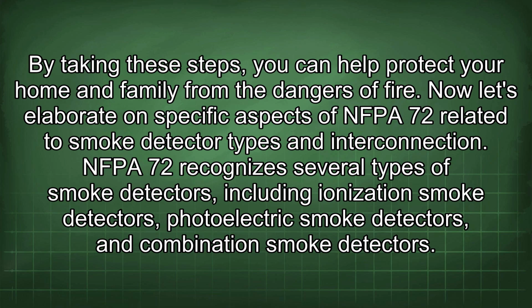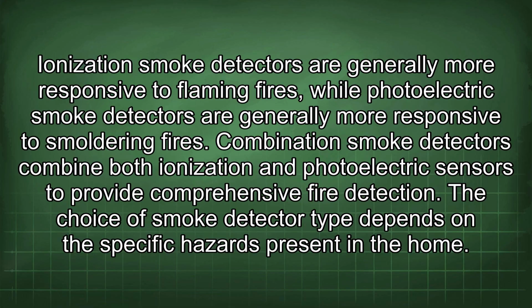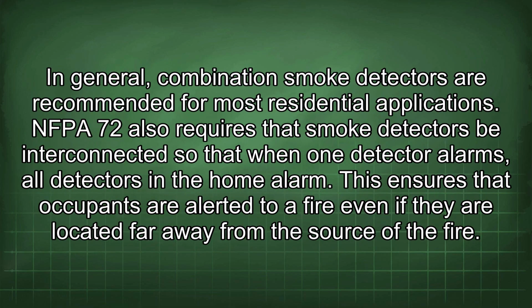Now let's elaborate on specific aspects of NFPA 72 related to smoke detector types and interconnection. NFPA 72 recognizes several types of smoke detectors, including ionization smoke detectors, photoelectric smoke detectors, and combination smoke detectors. Ionization smoke detectors are generally more responsive to flaming fires, while photoelectric smoke detectors are generally more responsive to smoldering fires. Combination smoke detectors combine both ionization and photoelectric sensors to provide comprehensive fire detection. The choice of smoke detector type depends on the specific hazards present in the home. In general, combination smoke detectors are recommended for most residential applications.